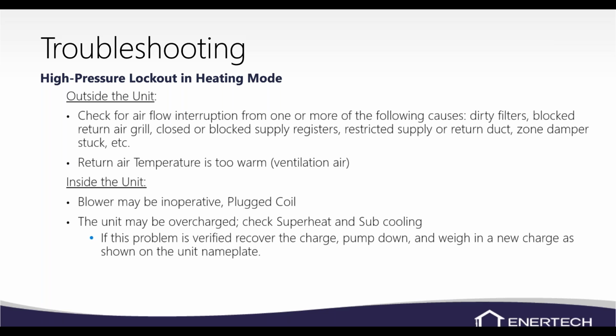If you don't really understand your superheat and subcooling real well, you're not real familiar with it, you can always remove the charge from the system and weigh it out. And there's a weight of refrigerant on the unit itself, and you can compare the numbers, and that'll tell you if it's low on refrigerant. But superheat and subcooling will tell you that as well.